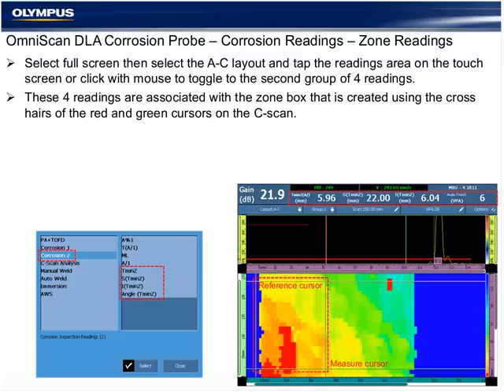All of the readings that include a Z mean they're relative to the zone. The zone is created similar to how I validated the thickness readings using the ASTM calibration standard I demonstrated earlier. If I create a zone with the crosshairs of the 2 cursors on the C-scan, within the zone I can see that the lowest reading was 5.96 millimeters, and it occurred at 22 by 6 millimeters on A-scan or virtual aperture number 6. And I could go look at that individual data point.